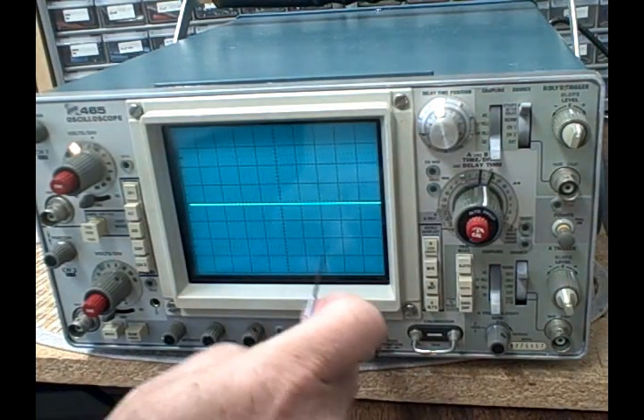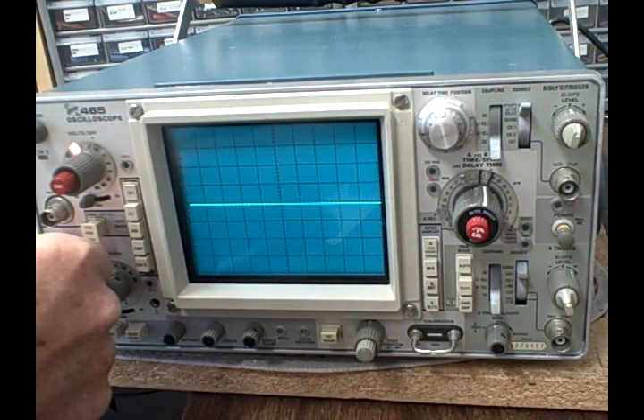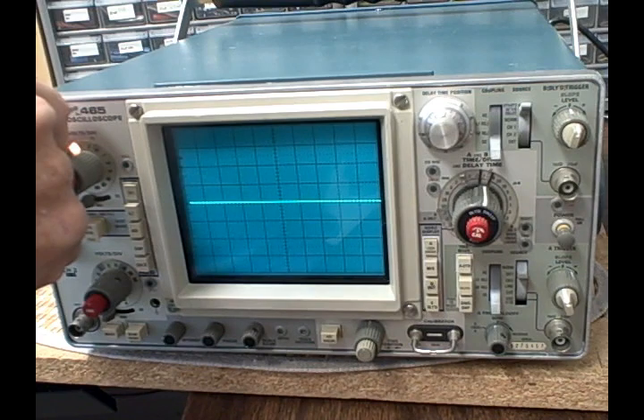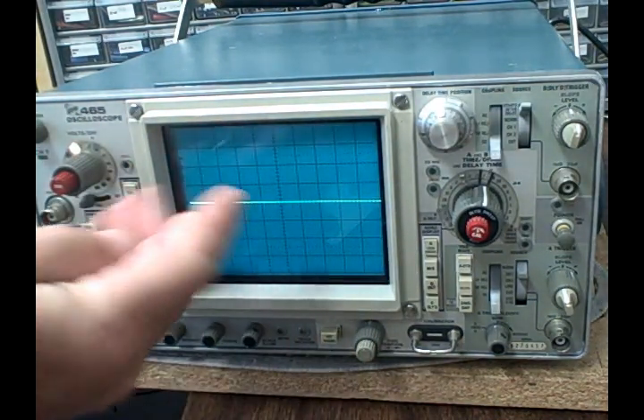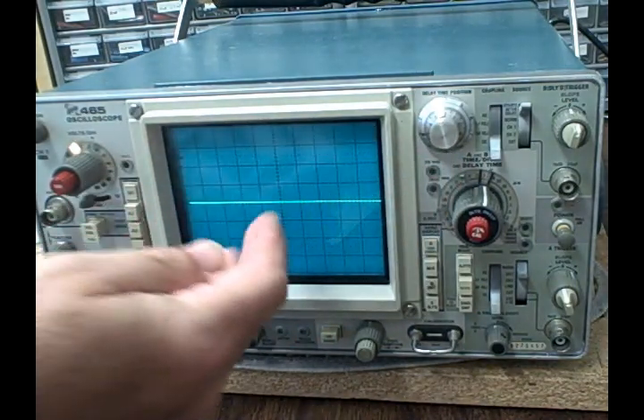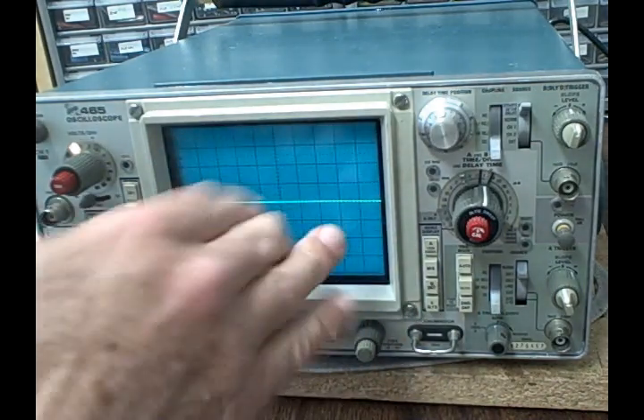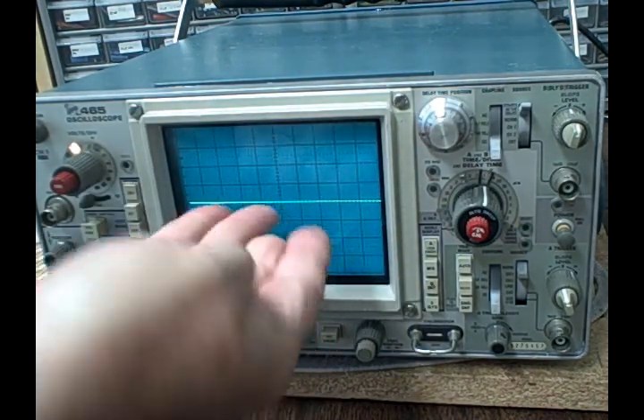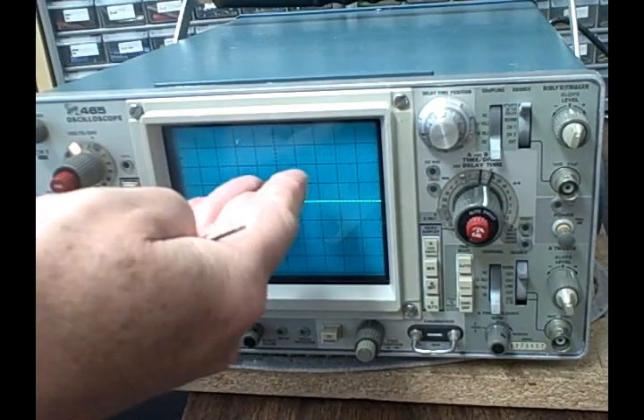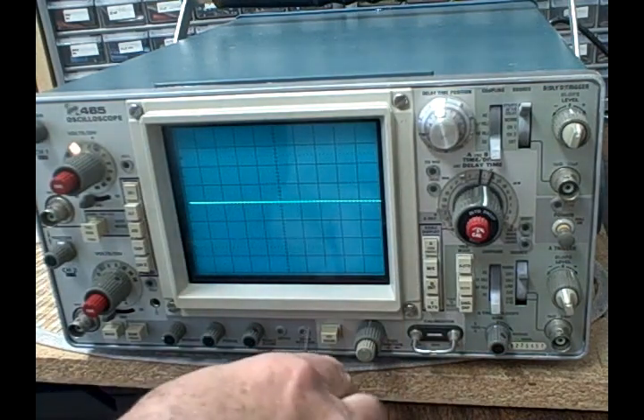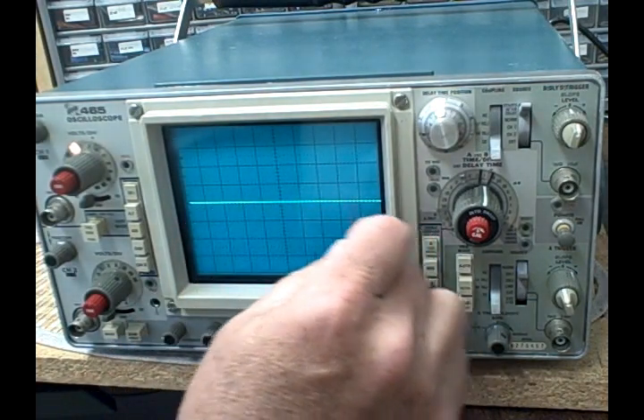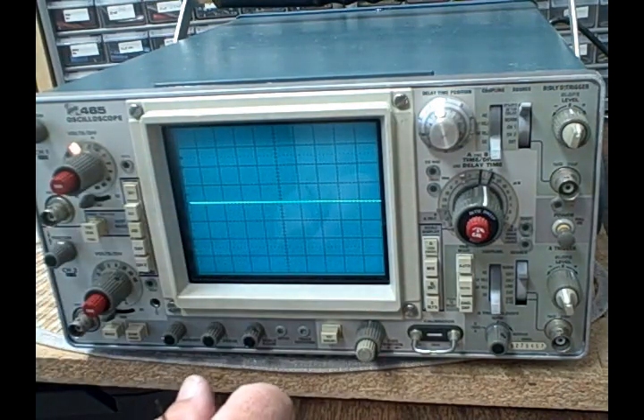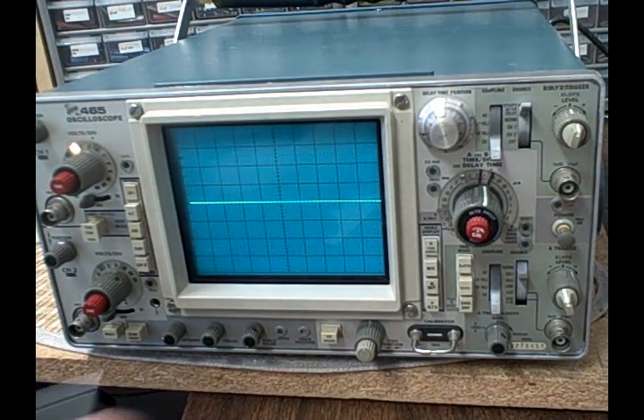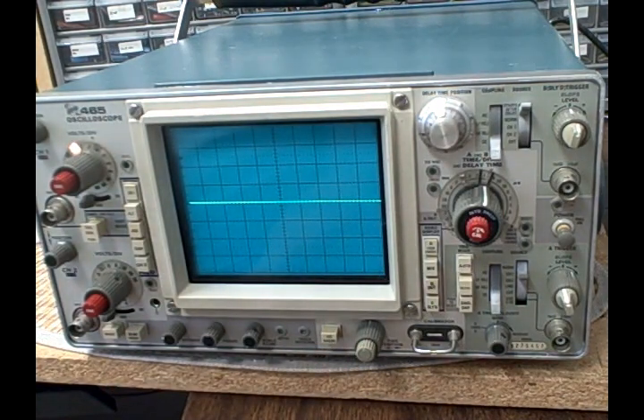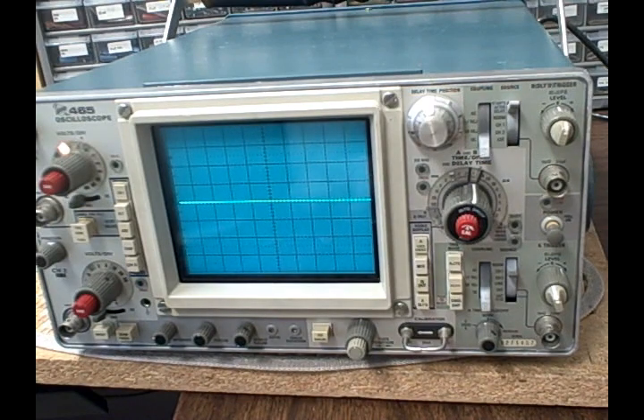Then the other thing you have here is trace rotation. And you use that, like right now our trace is perfectly flat. But let's say that the trace veered off on the right end and it actually rose above the line. Well, that's because that trace needs to be rotated slightly one way or the other. In order to counteract that trace going this way, you rotate the control so you lower it. And that's what the trace rotation does. You make it so you get the most even line there, when you're not feeding a signal in, and that's going to make sure that you have a good trace. But that's a feature that's nice to have handy right there on the front. So that pretty well does it.